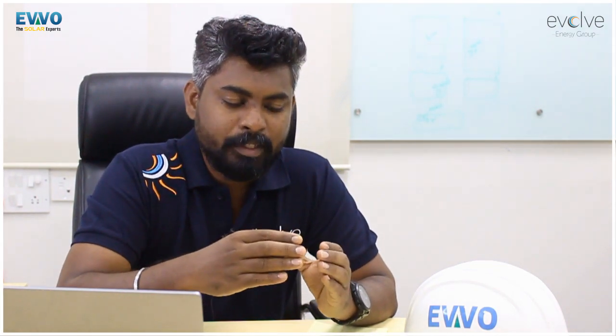Now for a galvanically isolated system, whether you ground it on the DC or AC, it doesn't really matter, because both are galvanically isolated. But our solar power systems are non-galvanically isolated, so that is one main reason you have to ground the DC side as well as the AC side. They both have to be grounded separately.